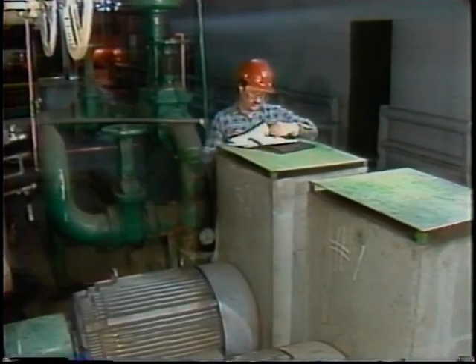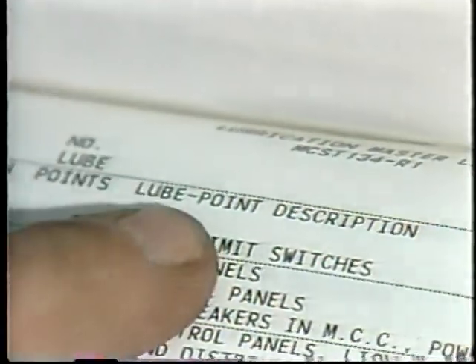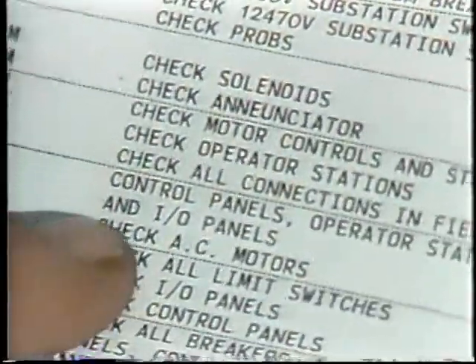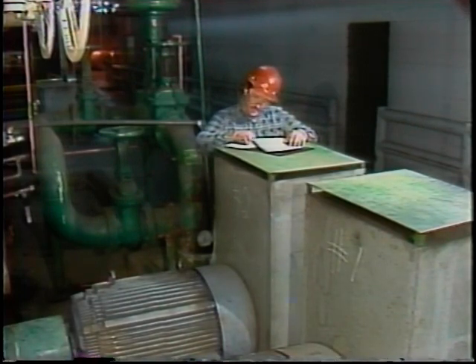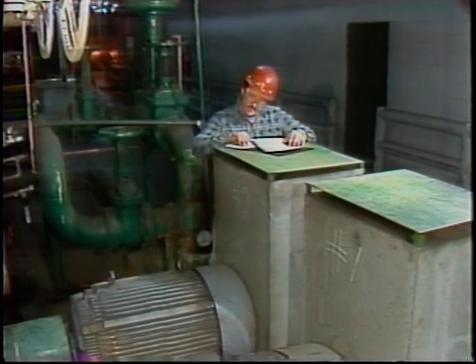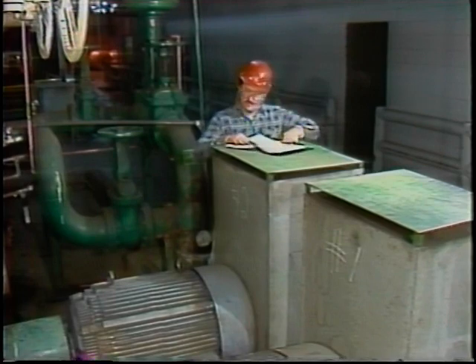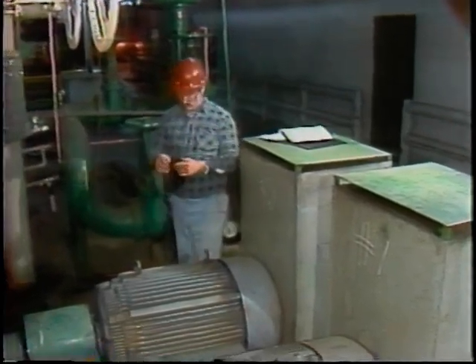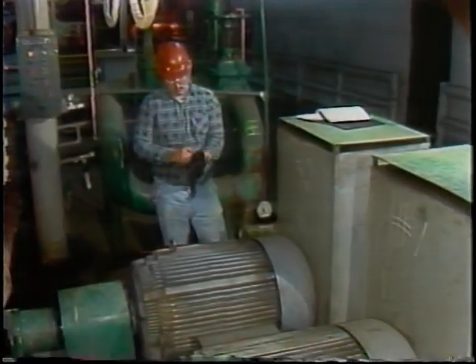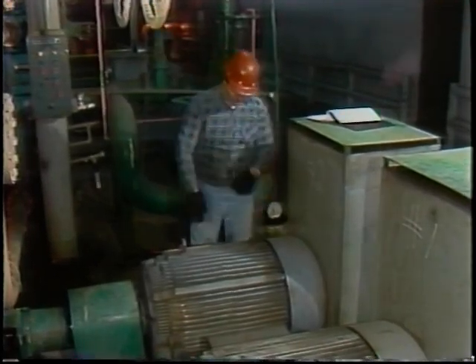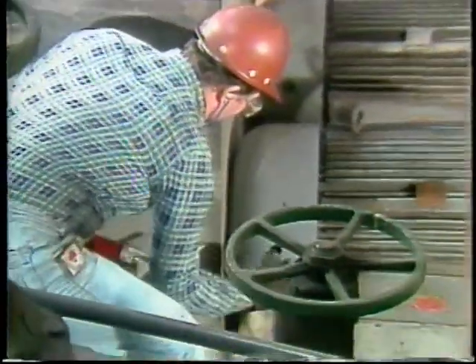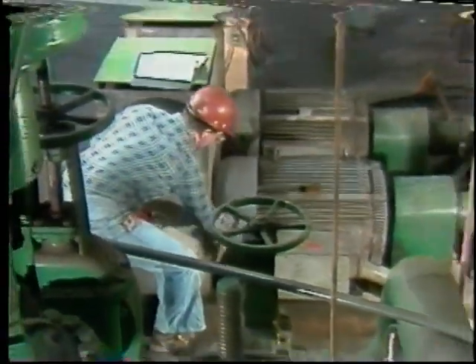It should tell you when to lubricate the bearings, for example, and what kind of lubricant to use. Do not lubricate more often than recommended, and do not over-lubricate. Too much oil or grease in a ball or roller bearing will actually increase friction and heat, and probably leak out. Preferably, the motor should be warm and running. Be sure no dirt gets in the bearing along with the oil or grease, and wipe up excess or spilled lubricant. Look and listen while you work.